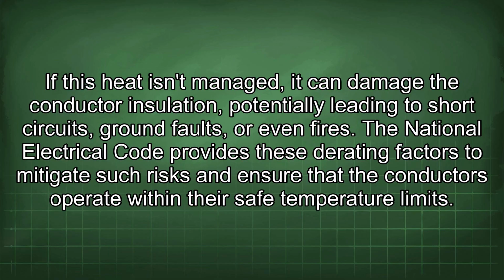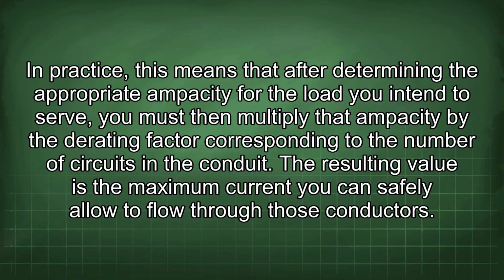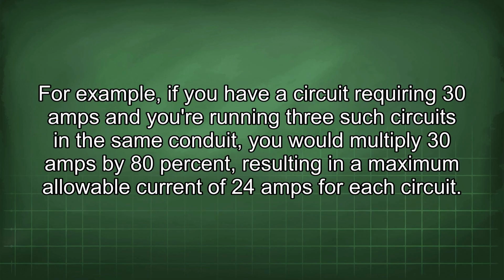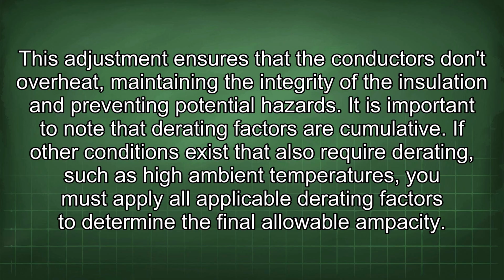their safe temperature limits. In practice, this means that after determining the appropriate ampacity for the load you intend to serve, you must then multiply that ampacity by the derating factor corresponding to the number of circuits in the conduit. The resulting value is the maximum current you can safely allow to flow through those conductors. For example, if you have a circuit requiring 30 amps and you're running 3 such circuits in the same conduit, you would multiply 30 amps by 80%, resulting in a maximum allowable current of 24 amps for each circuit. This adjustment ensures that the conductors don't overheat, maintaining the integrity of the insulation and preventing potential hazards.